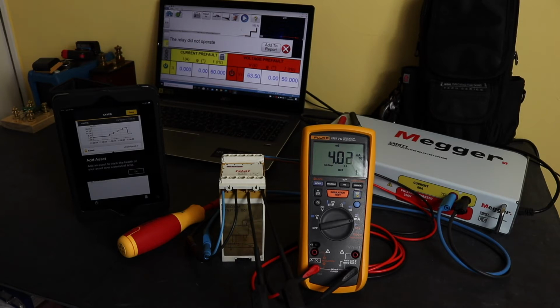Unfortunately, the SMRT is configured more for protection relay testing and not really transducer testing, or if it is for transducer testing, I haven't figured it out yet. And I can't get rid of that error message. It doesn't mean anything because I'm just recording this as the input really, so I can just accept that and get rid of that. And there you see I can have the result displayed upon the screen, and what I'll be able to do now is export this out either as a PDF report, or what I will do is put it into Excel so that I can do some more analysis on the readings, which I'll show on the computer now.